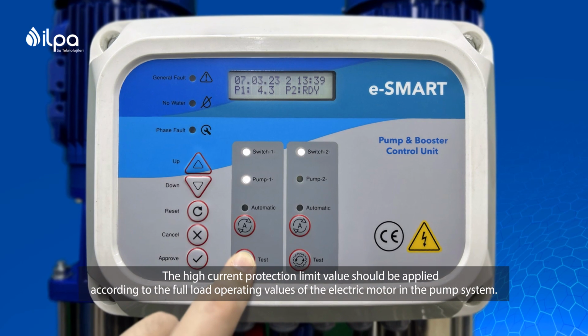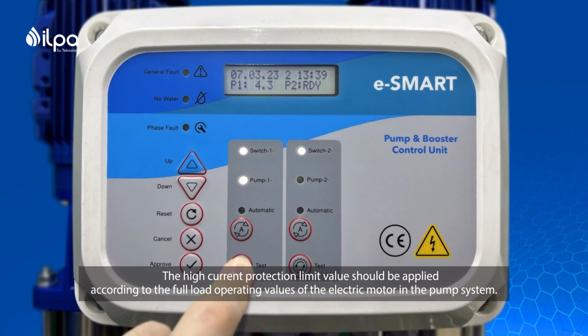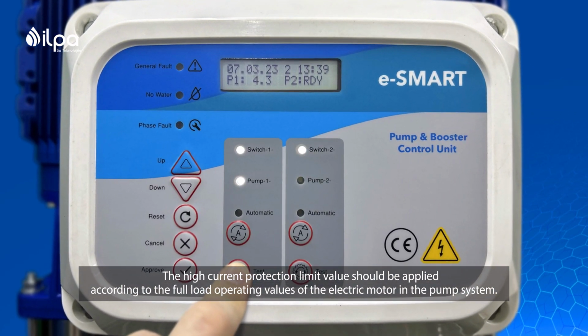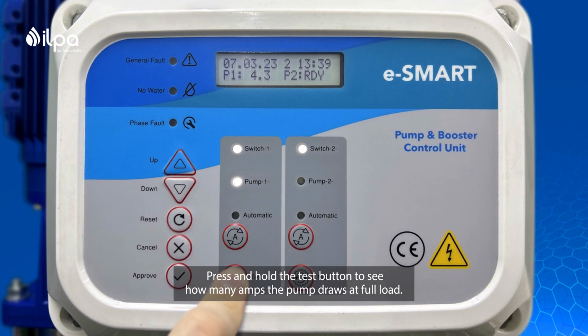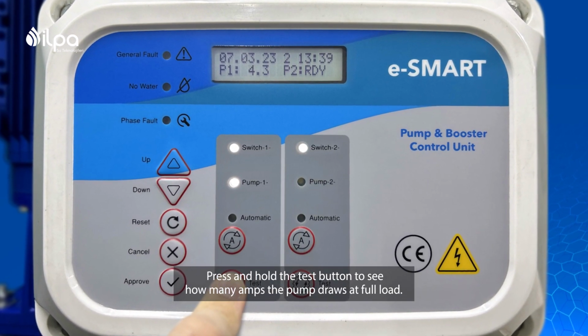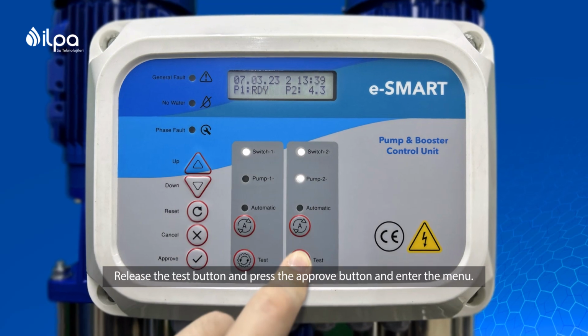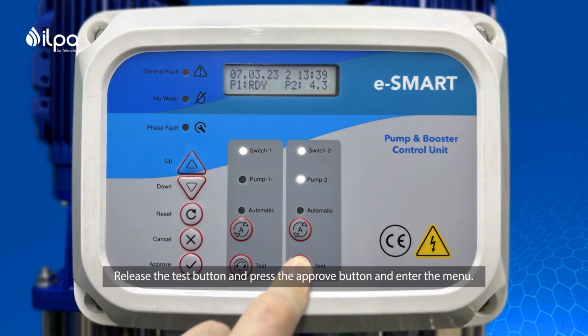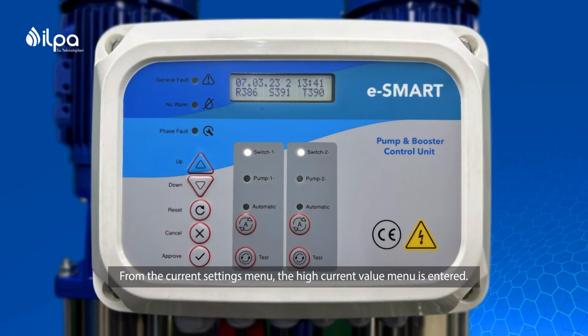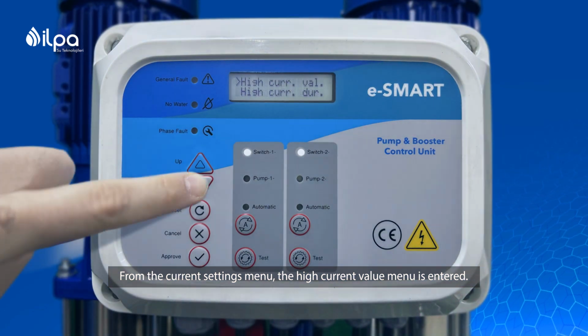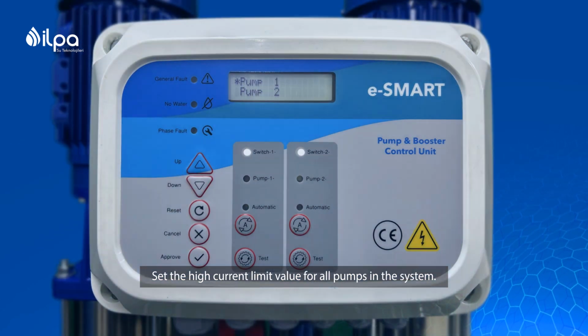The high current protection limit value should be applied according to the full load operating values of the electric motor in the pump system. Press and hold the test button to see how many amps the pump draws at full load. Release the test button, press the Approve button and enter the menu. From the Current Settings menu, the High Current Value menu is entered. Set the high current limit value for all pumps in the system.